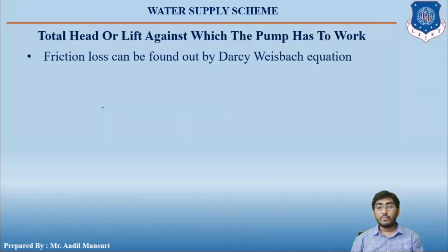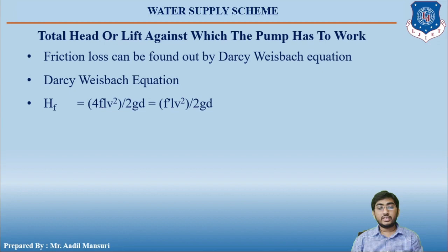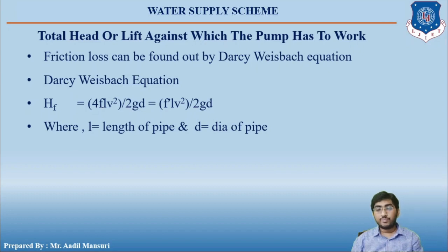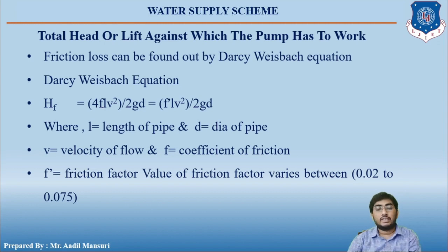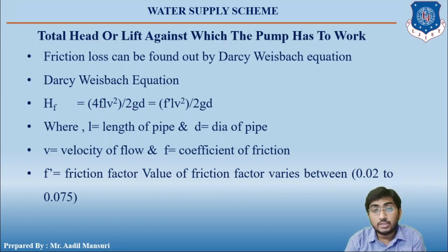Frictional losses can be found using the Darcy-Weisbach equation: hf = 4fLv²/2gd, or hf = f'Lv²/2gd, where L is the length of the pipe, d is the diameter, v is the velocity of flow, and f is the coefficient of friction. When 4f is replaced by f', then f' is the frictional factor, whose value varies between 0.02 to 0.075.